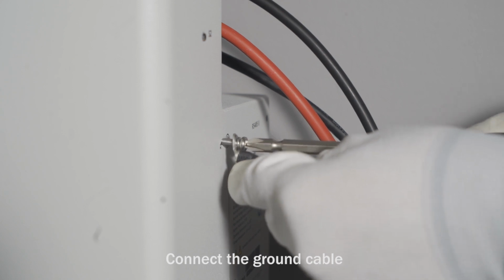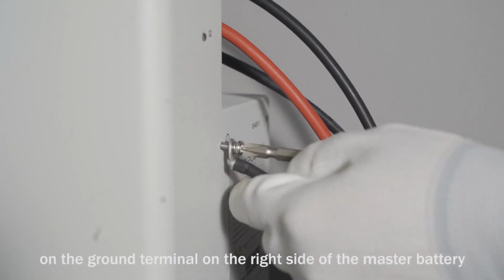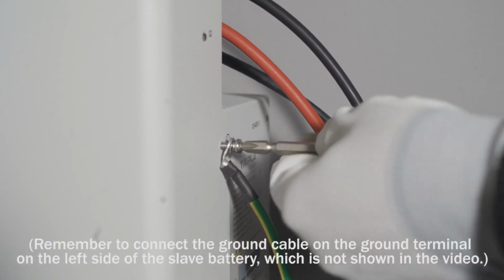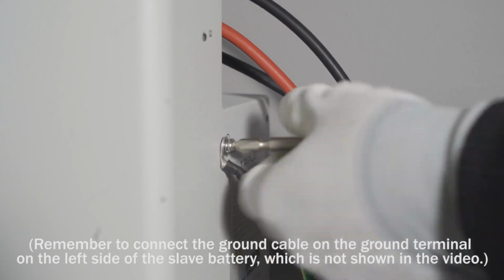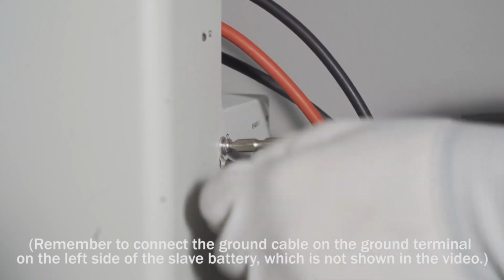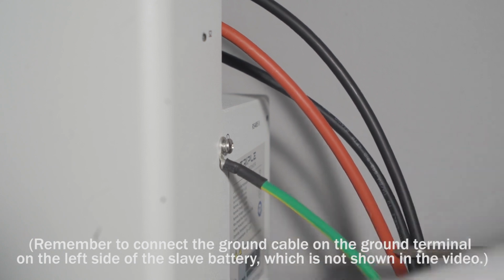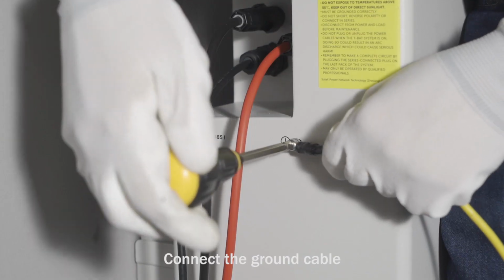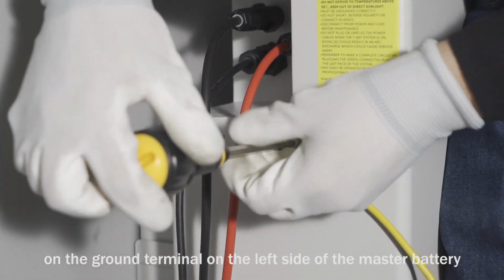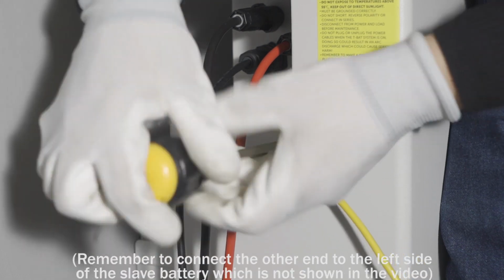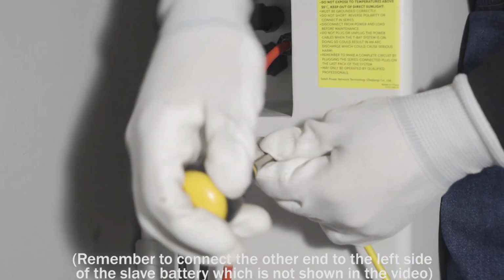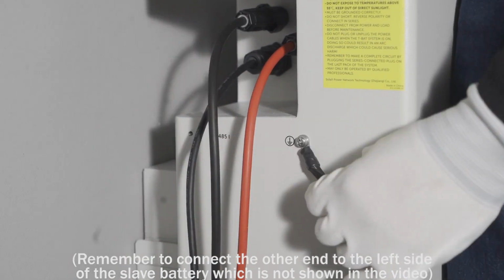Connect the ground cable on the ground terminal on the right side of the master battery. Remember to connect the ground cable on the ground terminal on the left side of the slave battery, which is not shown in the video. Connect the ground cable on the ground terminal on the left side of the master battery. Remember to connect the other end to the left side of the slave battery, which is not shown in the video.